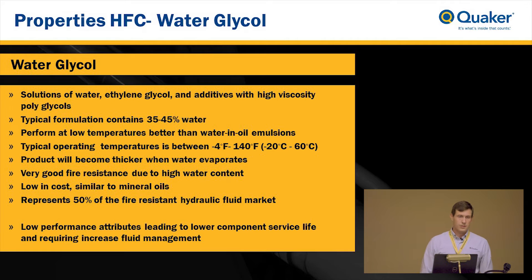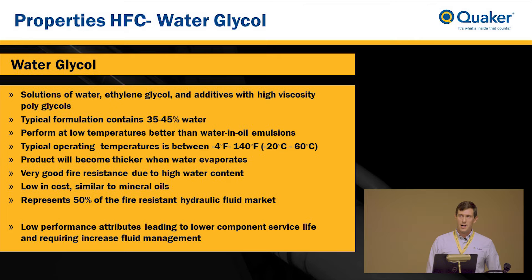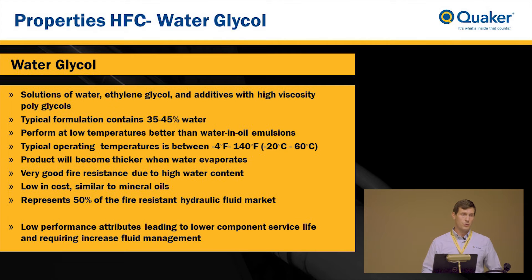The third is HFC water glycols. As the name suggests it contains water and also a glycol — ethylene glycol and different other chemicals that are put into it to get the proper viscosity. This makes up about half of the fire resistant market in total because it has a very low temperature range, making it ideal for antifreeze applications. In this area for longwall shields underground, the storage fluid would be a water glycol.